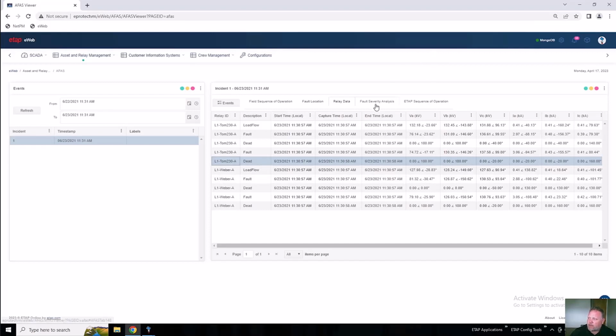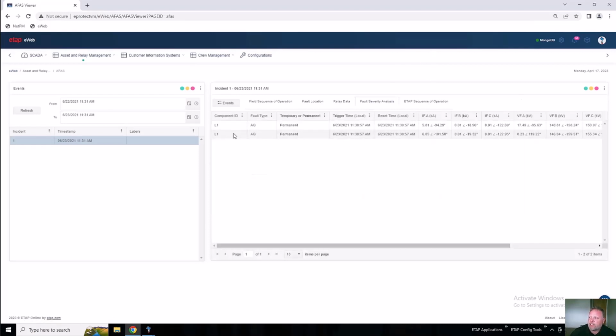Now, when I go into the fault severity analysis here, it may be confusing, but there are two faults. There are two elements in this, both on line 1. That's because this is not a temporary fault, it's a permanent fault. And here we show the times that these different events happened, the fault current and the fault voltage.